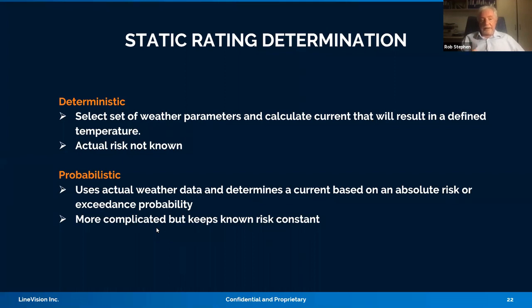Now, this is still a static rating because it'll give you a rating which doesn't change by the hour or by day. You can get a seasonal rating, but then the season is defined from a particular date. It's more complicated than a deterministic rating because now you've got to do a lot more computations. With a probabilistic rating, for example, we use 30 to 40 years of data and most probably a couple of hundred weather stations around a particular country. So you'd need to be able to do quite a lot of computer analysis and then also relate that to a probability of an unsafe condition arising. And all this is covered within the CIGRE documents, which are now international documents. Next slide, please.